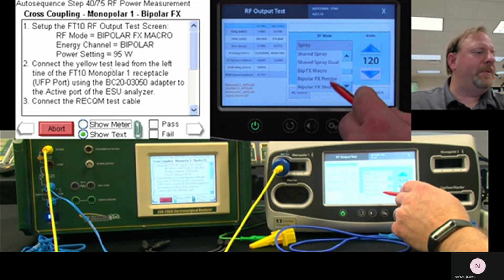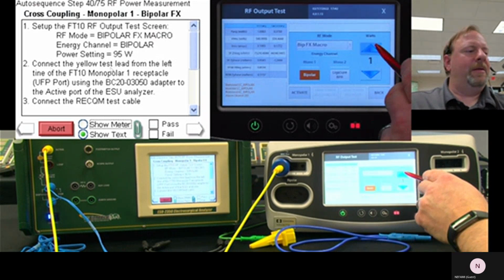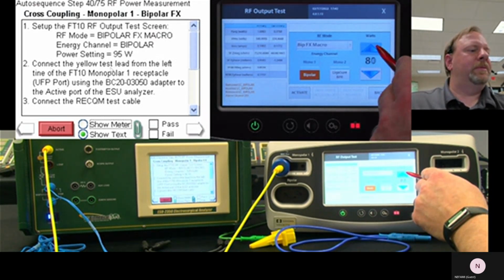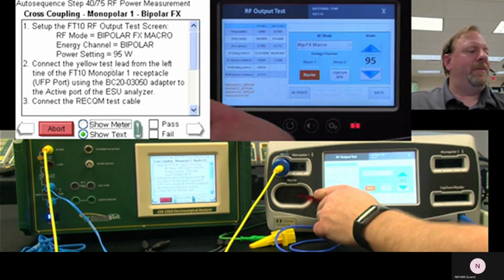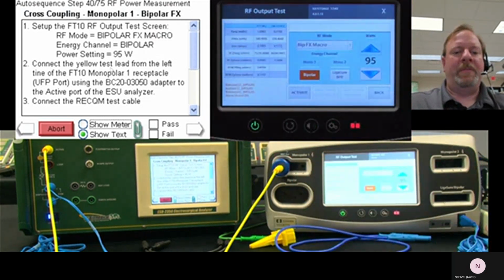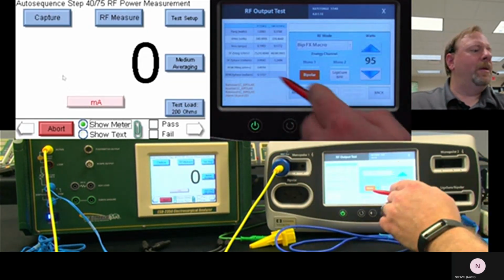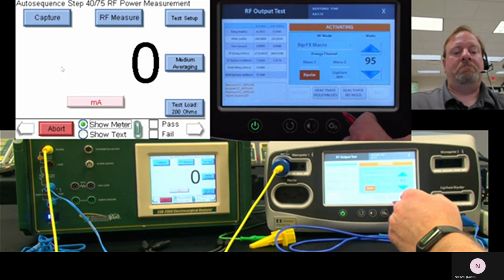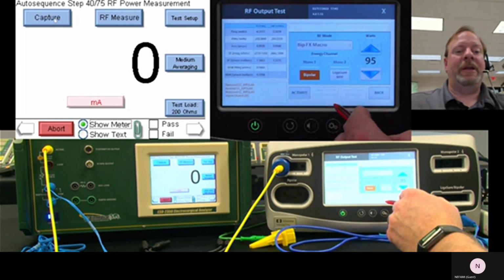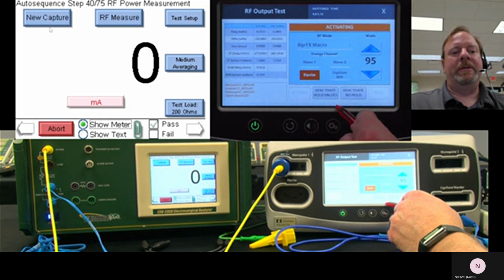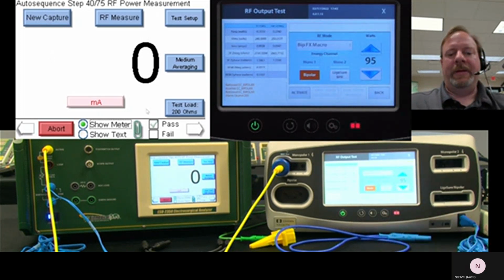Bipolar macro. That's important. Max power. Now I'm activating bipolar and I'm measuring off a monopolar. Activate. It's pretty good. We got absolutely nothing. Oh, got to capture that. Absolutely nothing. That's a pass.